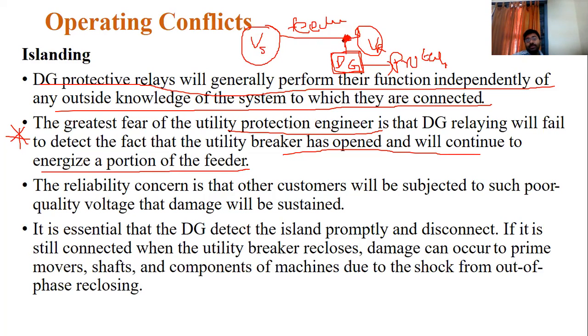Okay, in that case, what will happen? This feeder relaying is open, but still this DG is connected to these loads. You can understand here the basic, very simple thing. Two different protective schemes are available here. First one is the feeder protective scheme, to protect the feeders or distribution lines and all other things. What is the second case? A DG protective scheme is available to disconnect the DG from any unwanted changes in the feeder. These are the two cases.